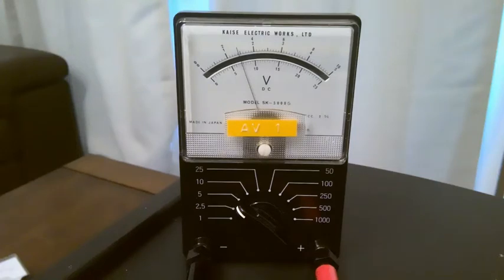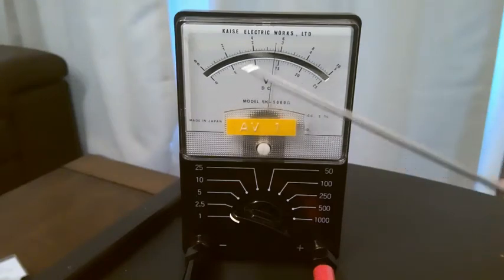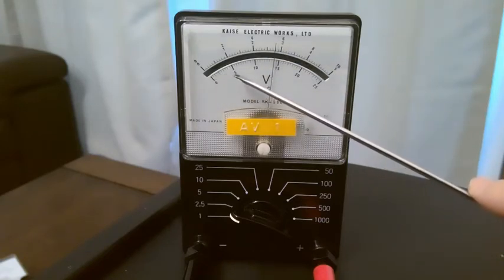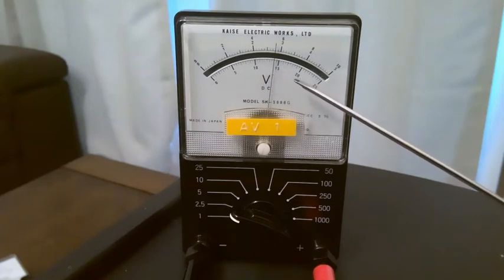Because this voltage is less than 2.5 volts, we can actually use a smaller, more sensitive scale. So we are going to switch to 2.5 volts and try to read this voltage again. This time the full span is 2.5 volts. If you look at these 3 scales, they are 10, 5, and 25. So we don't really have a 2.5 volt reading there. The best we can do is use the bottom line, from 0 to 25. However, we want to read them as this, divided by 10. So 0, 0.5, 1.0, 1.5, 2.0, and 2.5 right there, which is the full span.